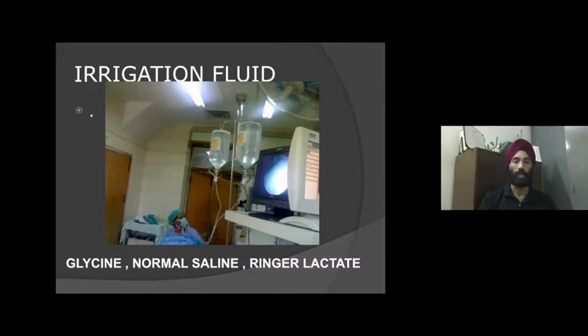There are commercially available arthro pumps which are water pushing devices which can push the irrigation fluid into the joint. More useful for arthroscopies in joints like the shoulder where you cannot apply a tourniquet. Less commonly used for knee arthroscopy. Advantage of glycine is that in addition to doing an arthroscopy, if you have to use a cautery device, you can cauterize. Though again in the knee, because of tourniquet availability, you don't need to use too much cautery, and hence we don't use glycine too commonly now.